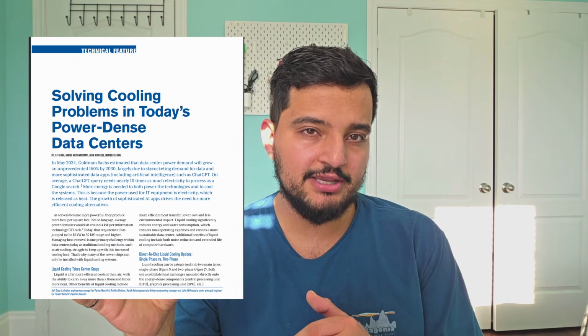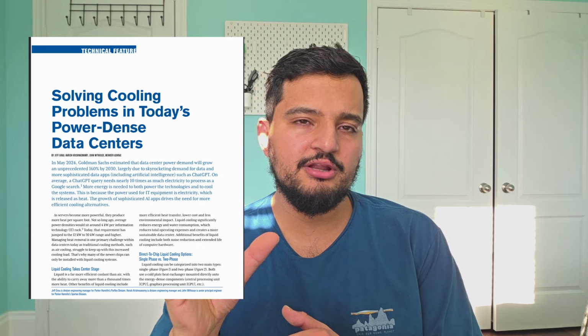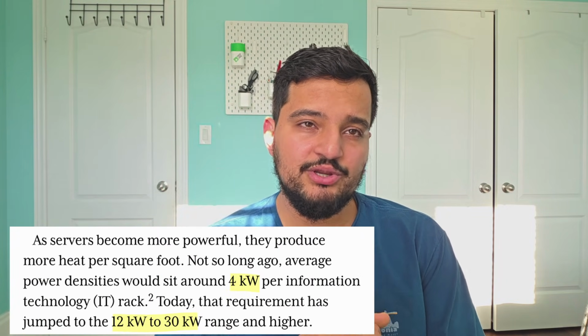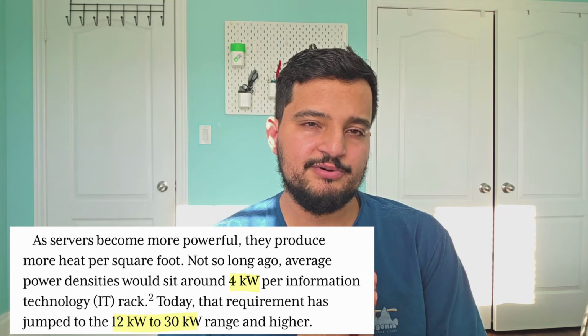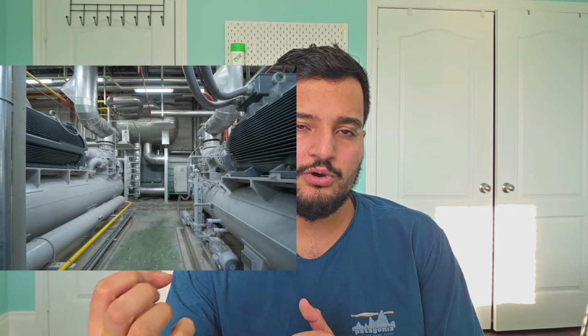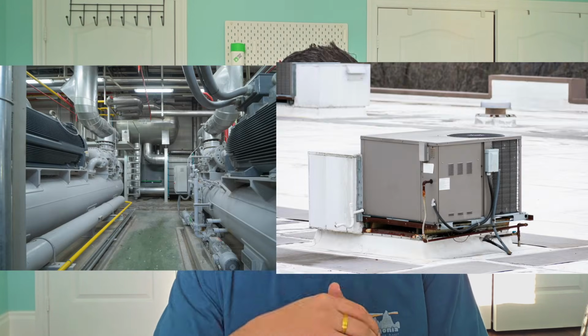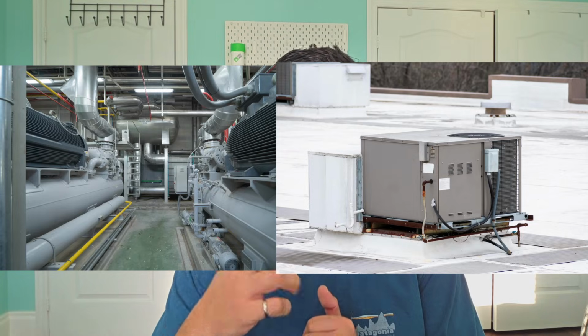According to ASHRAE, the power density of an average IT rack in a data center used to be around 4 kilowatts per rack. But with the advent of AI, this has jumped up to anywhere between 12 kilowatts and 30 kilowatts per rack, and even higher. For data centers with such high power density, the best option for cooling is actually a chilled water system as opposed to an air system. And this is where the water consumption really comes in. The principle of a chilled water system is simple.